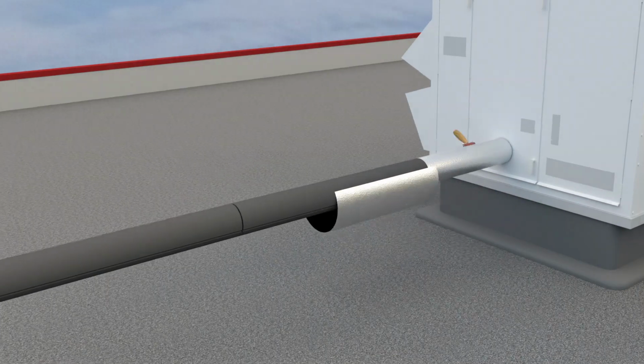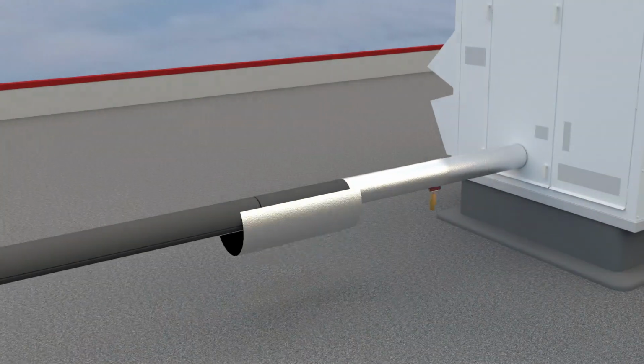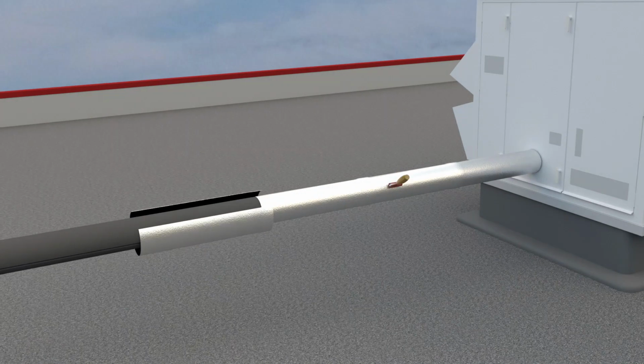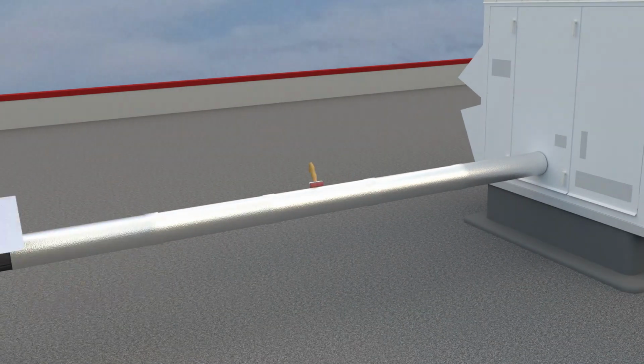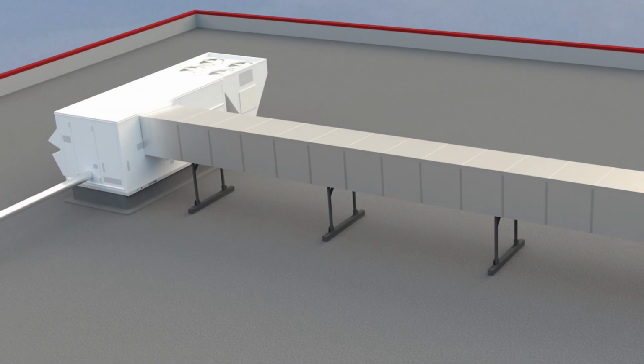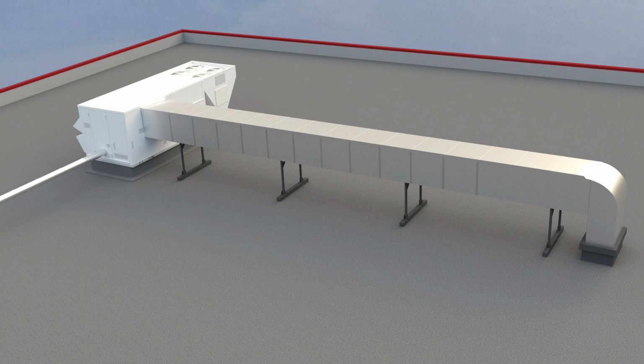Continue installing FlexClad in sections, making sure to overlap each section by at least 3 inches. Roll the entire membrane to ensure maximum contact of FlexClad to the insulation. Side laps can be caulked using an MFM-approved caulk or sealant. And this project is a wrap. No need for any special adhesives, coatings, or equipment to complete the job.